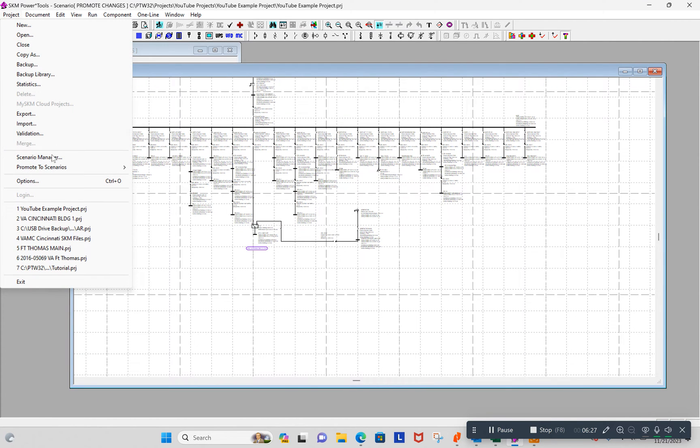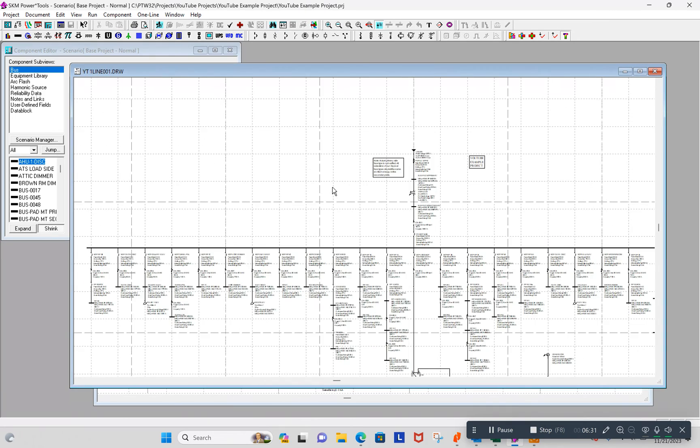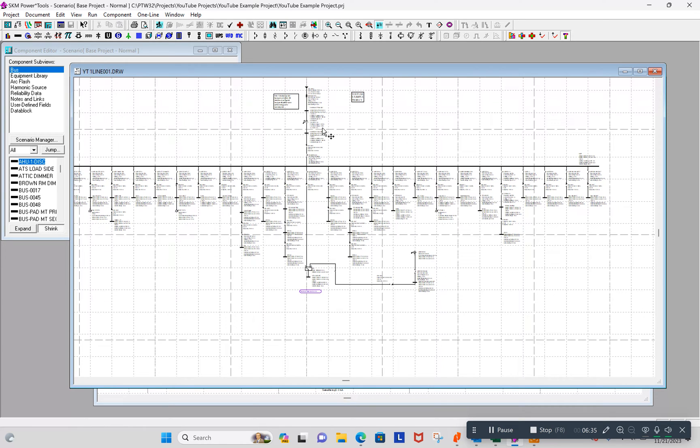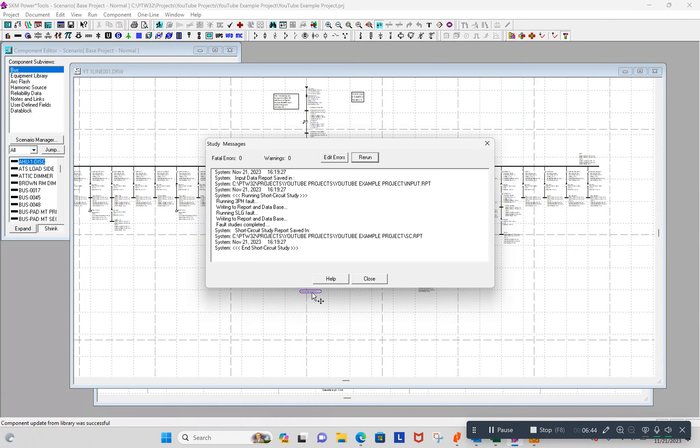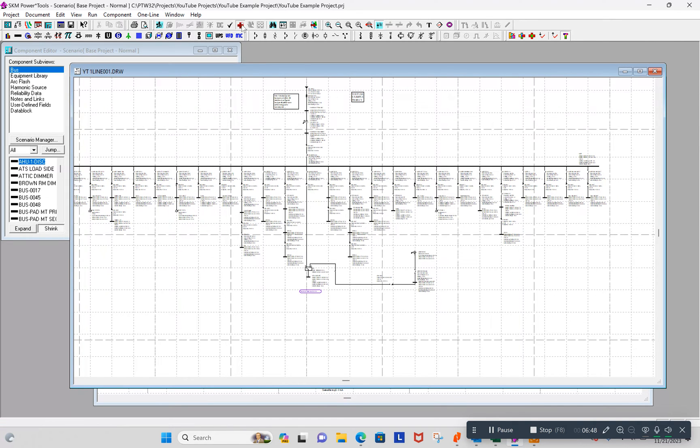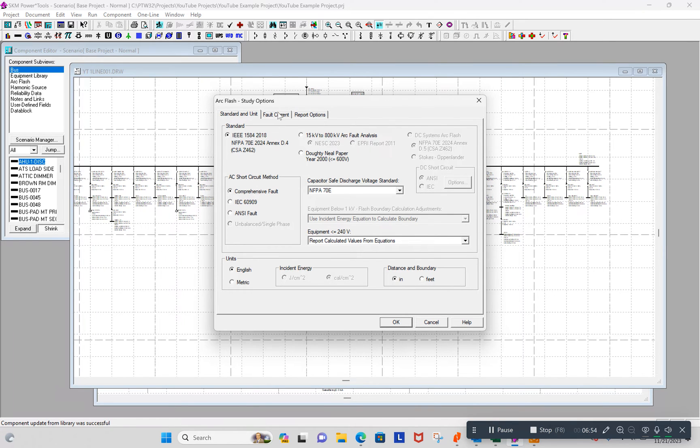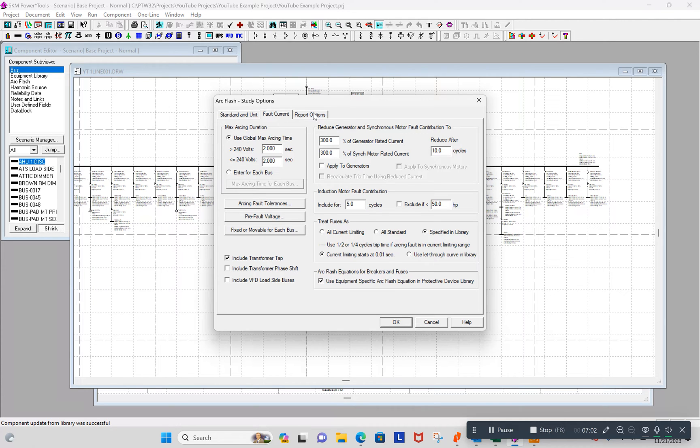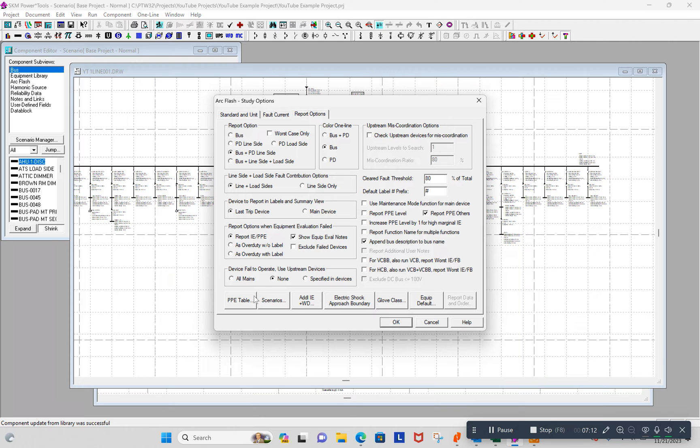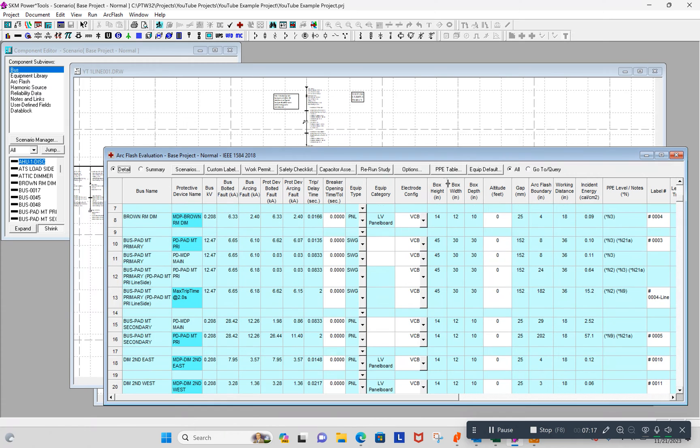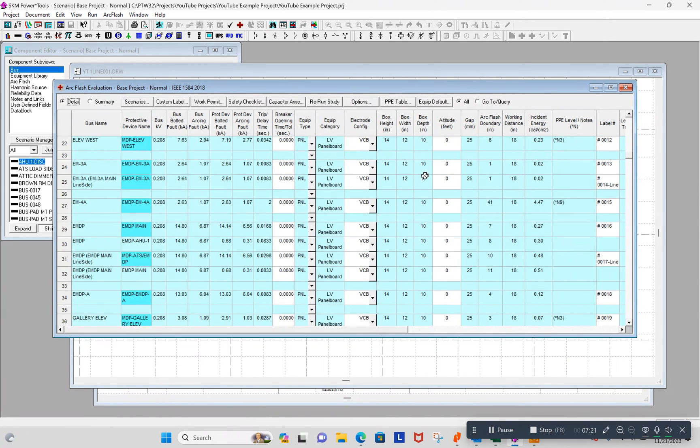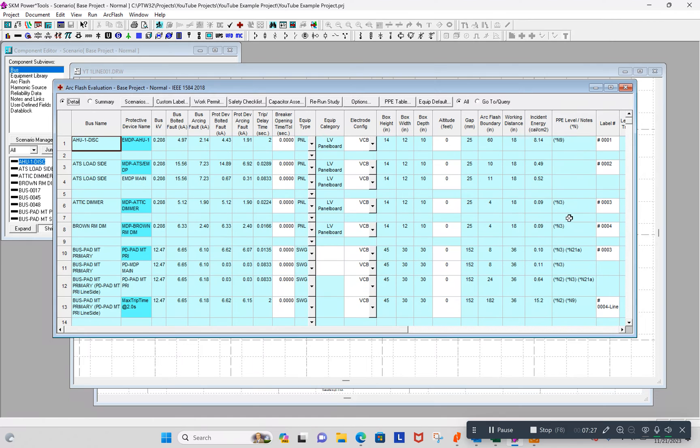Now let's do what the actual purpose of these scenarios are. So I'm going to go back to the base scenario. And I'm going to run my short circuit. I don't know. I haven't run this in a while. I don't know if I have errors or not. I don't have any errors, so that seemed to have worked. I'm going to do an arc flash study. Better on comprehensive, the latest 1584. I'm going to allow for the two second rule. Fuses will be as they're specified. That's okay. Okay. I've only got one scenario run here. It's the base scenario. So I don't have any nodes over here that's talking about S0 or S1 or anything like that.